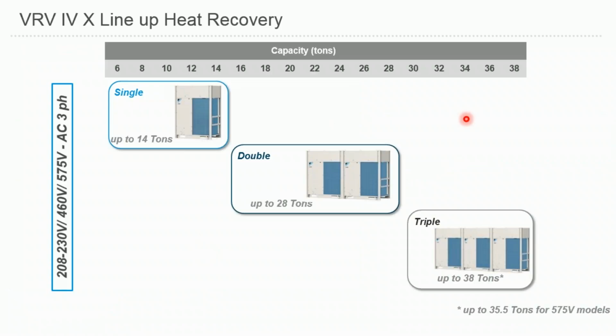From a capacity lineup standpoint, not much changing. We're still limited to 14 tons on the single module and up to 38 tons with triple module configuration. For the 575-volt model, because of these additional CRN requirements on the refnets, we're limiting our largest capacity to 35.5 tons. This is your nominal cooling capacity.